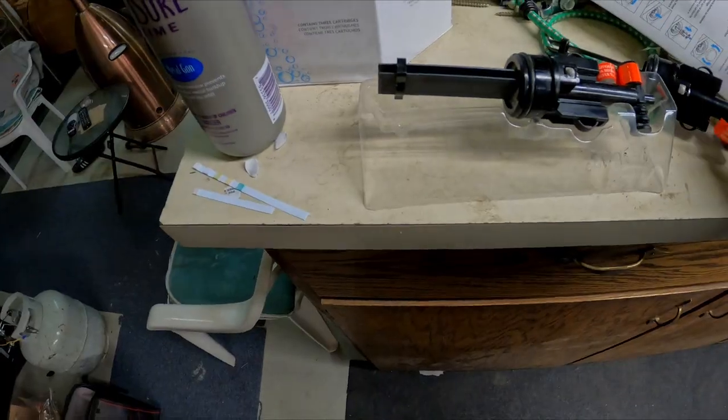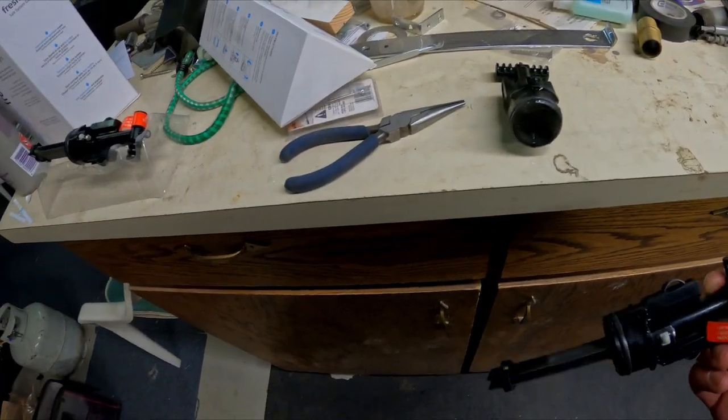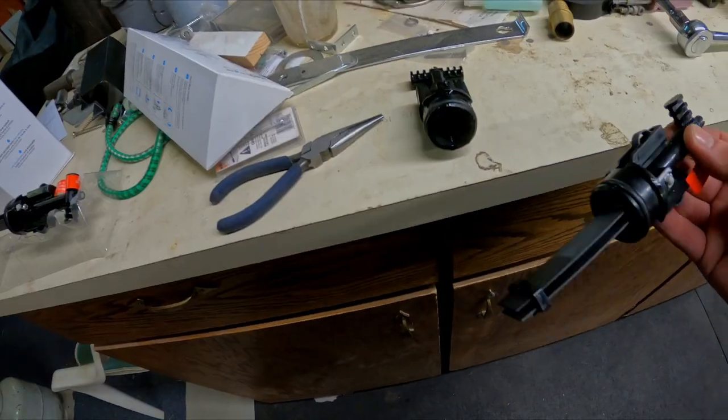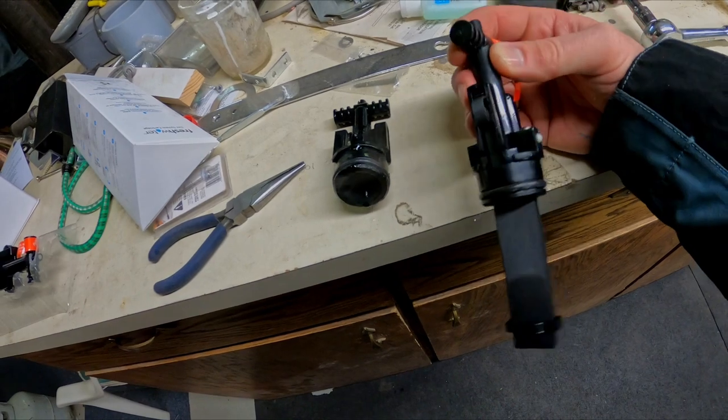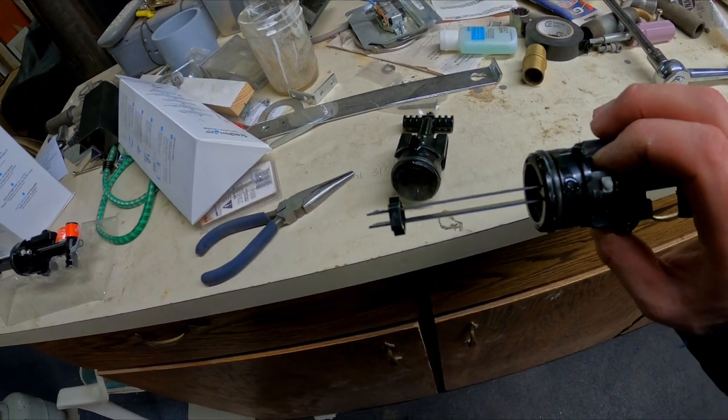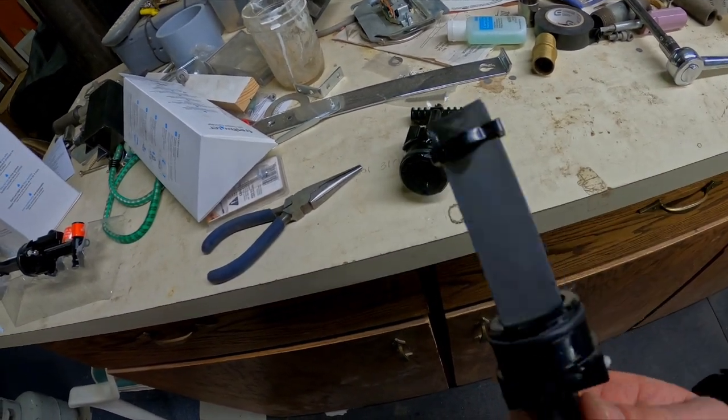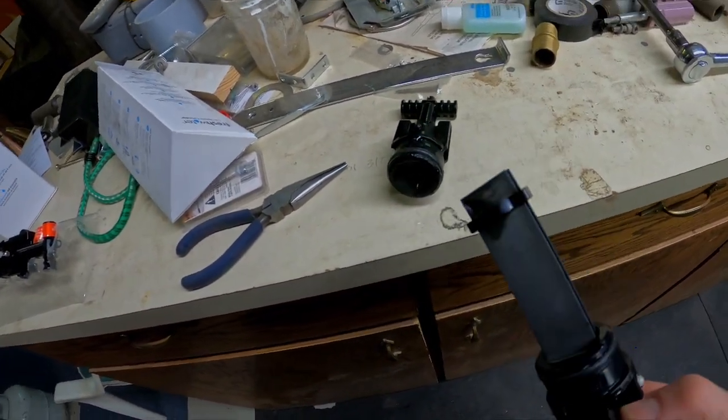A lot of times I will get this problem where the customer calls and they've said they've replaced their salt cartridge and their system isn't working anymore. What has happened is they have accidentally removed their salt cartridge and put their plug in and not even realize that it's not the same thing.